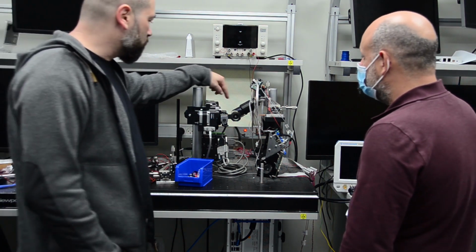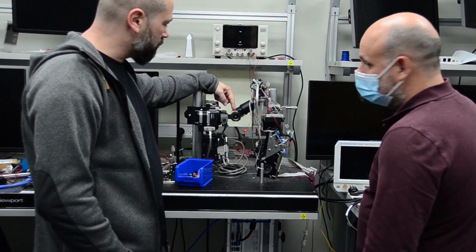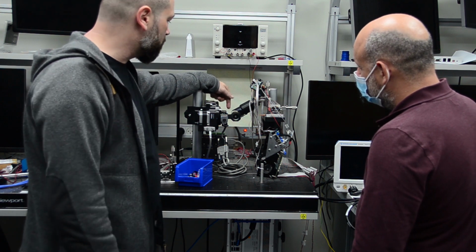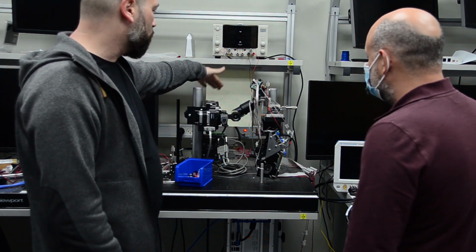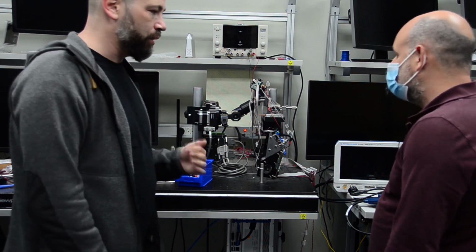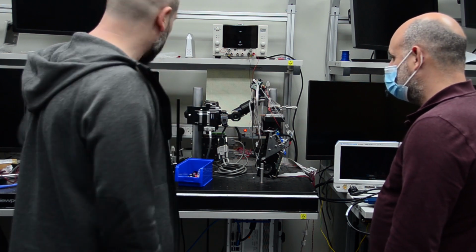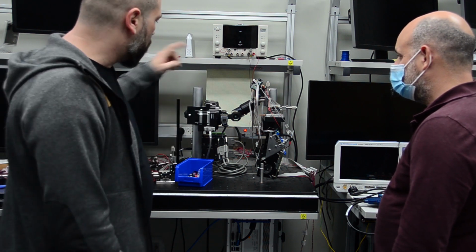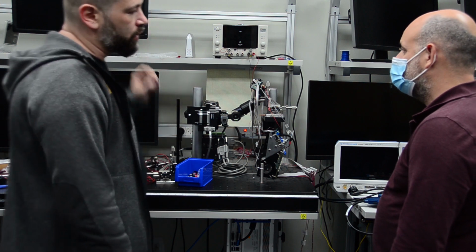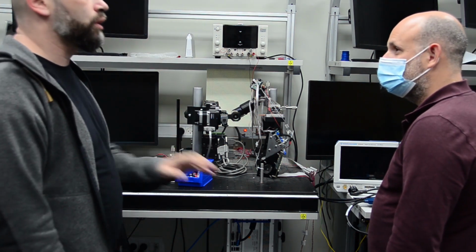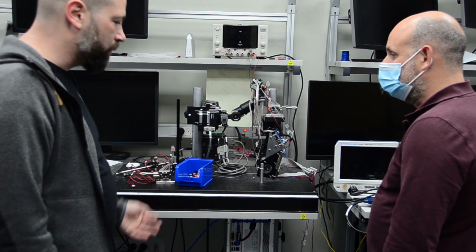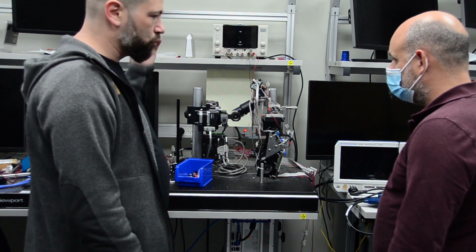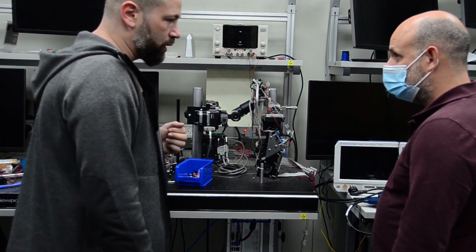Okay. Now what you see here, since the green laser hits the retina and goes back, and this is a see-through system, part of the green laser also escapes to the screen, and you can see the position of the beam on the screen. Before we track, if we actuate the eye, it will assume various angles. However, the beam does not move on the screen. That means that the eye is a very good retroreflector. It reflects the beam exactly to the angle from which it came. However, when we want to track, it should move according to the optical axis of the system.